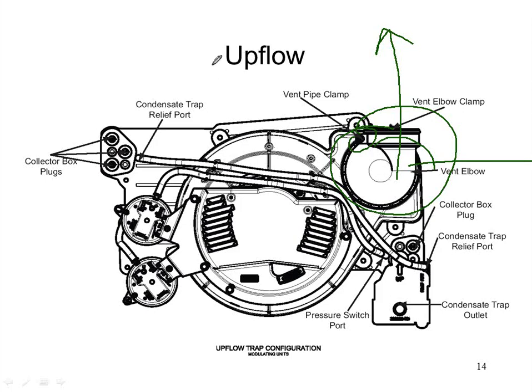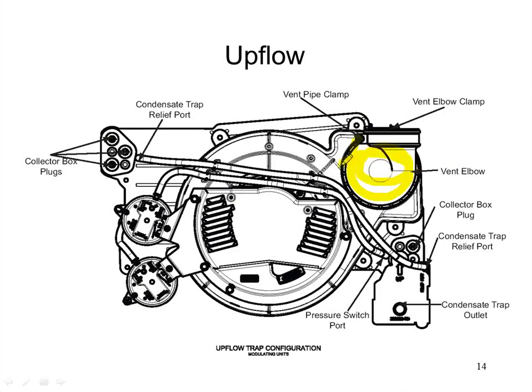I'm not going to vent him down in an upflow configuration, but if I flip the furnace upside down, then I would rotate the elbow 180 and down becomes up, if you will. So if I want to rotate this entire furnace and throw it on its left side, its right side, or completely upside down and make it a downflow, I do have to change that venting elbow. That's for sure. That's this guy right here, right?